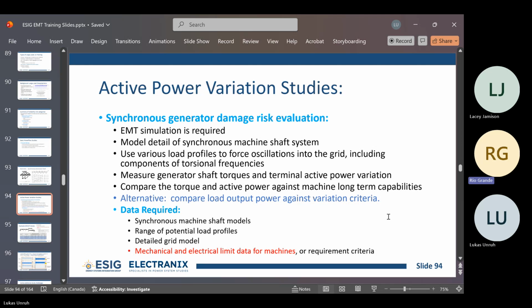It might occur every half second. It might occur every 2 seconds. But they'll give you an idea of the general shape, but they won't really commit to the, let's say, harmonic content of the profile. They might commit to a maximum amount of fluctuation. They'll say there are some methods that they can use to limit the bottom of those variations to some level. But in terms of the harmonic content, what we're hearing is that it's very difficult for them to commit to staying out of a certain frequency range, for example, or staying within some other frequency range.